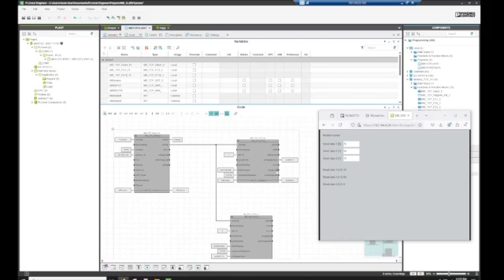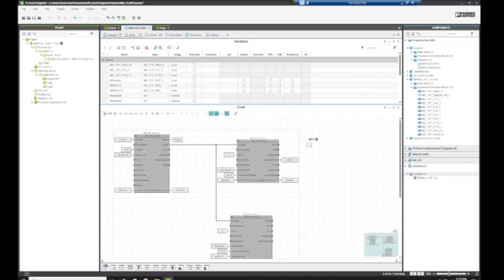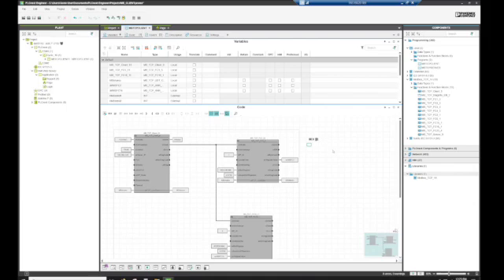So our start register is going to be 0 and our quantity of registers is going to be 3. So if I had five data points here it would be 5, if I only had one data point it would be 1. So it's only reading the chunk that you've asked it to. You're not reading a thousand parameters when you only need to read 2. And then it's putting them into this array which is an array of words.